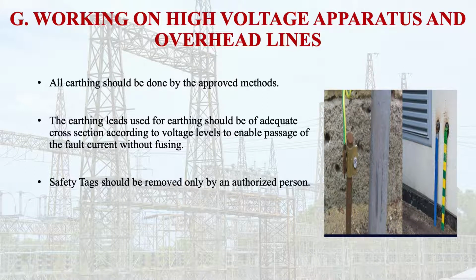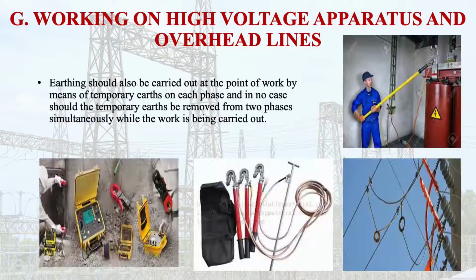Safety tags should be removed only by the authorized person. No other person is allowed for that. Then earthing should also be carried out at point of work by means of temporary earths on each phase. And in no case should the temporary earths be removed from two phases simultaneously while the work is being carried out. Remember this thing. Now let us discuss working on lower portion of towers carrying live lines.